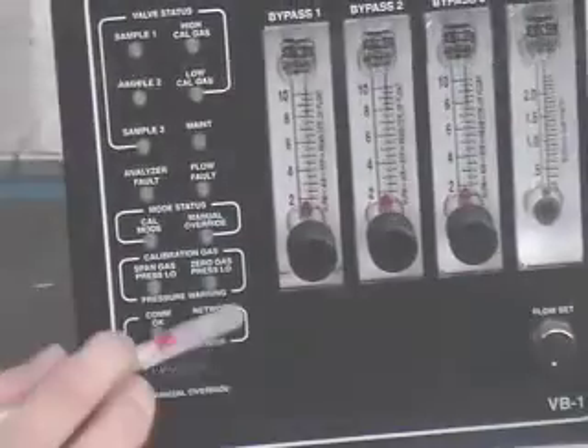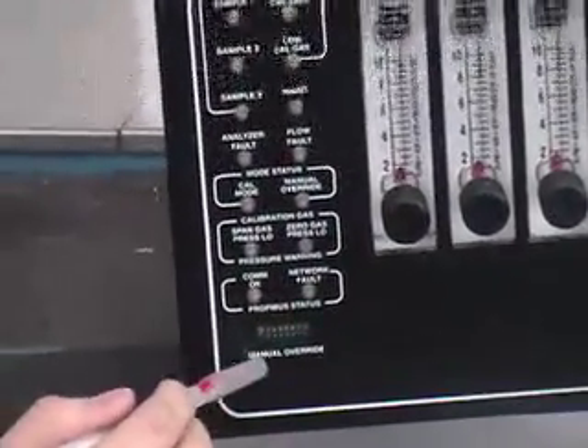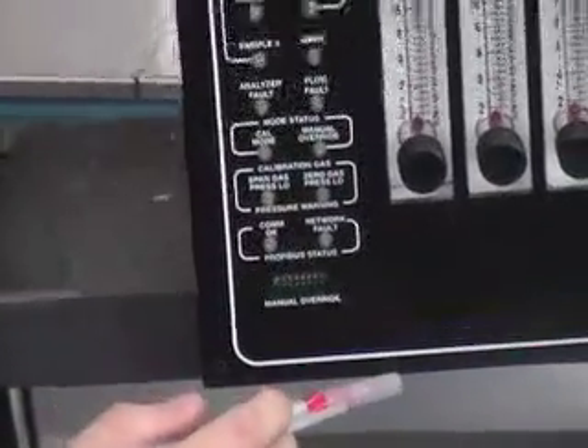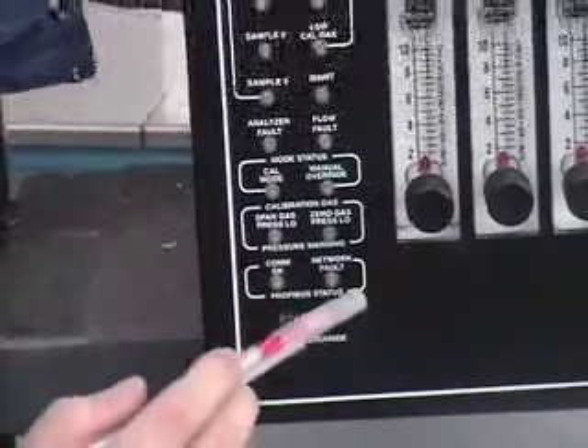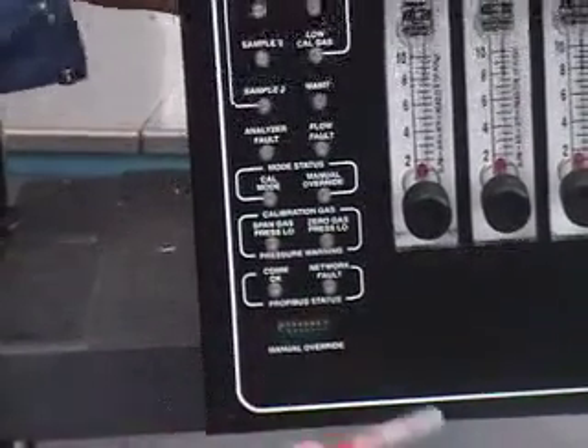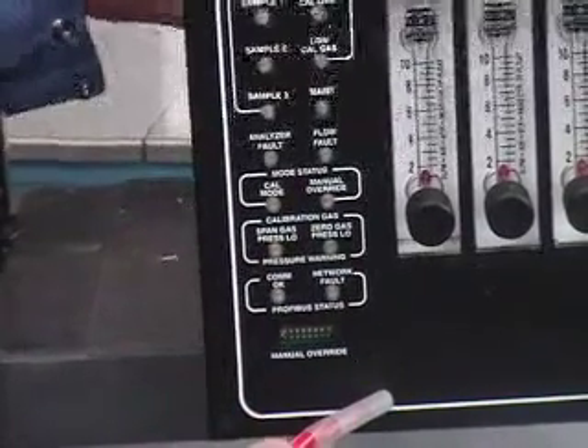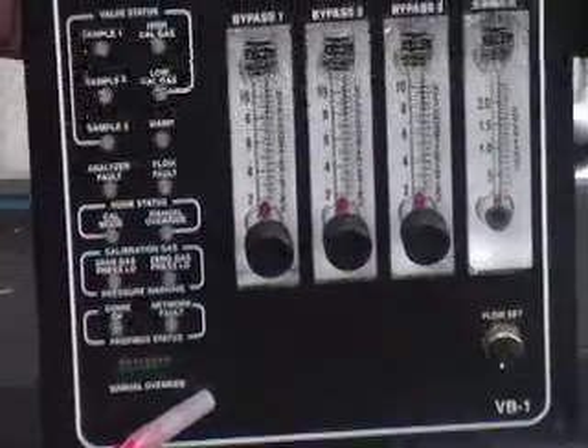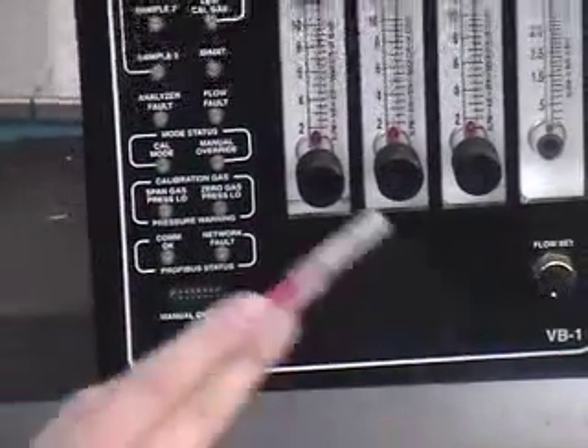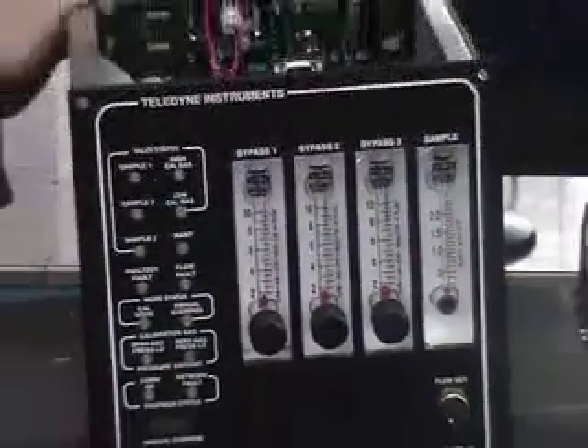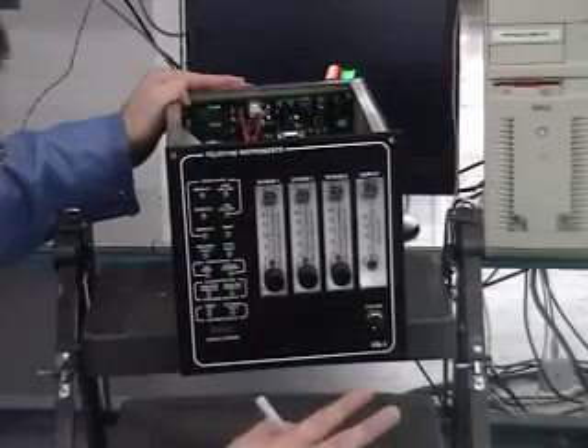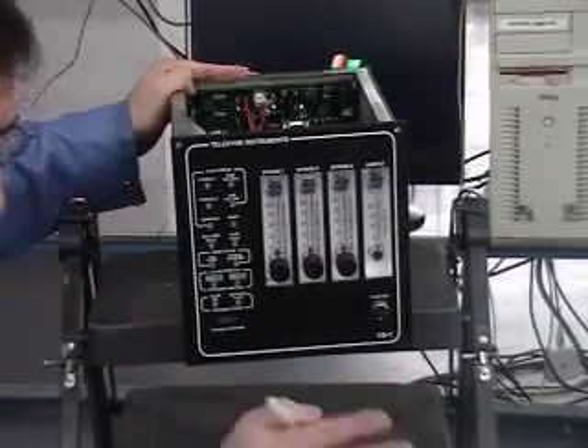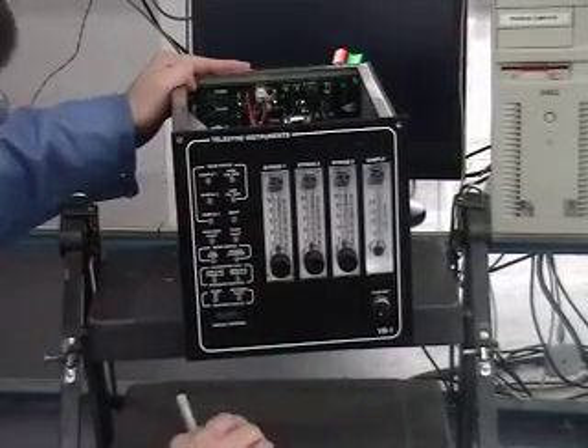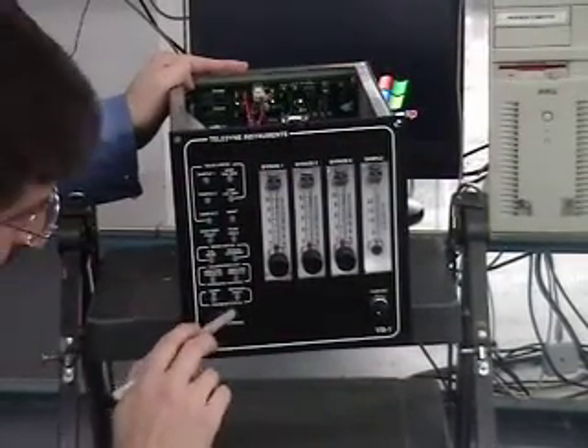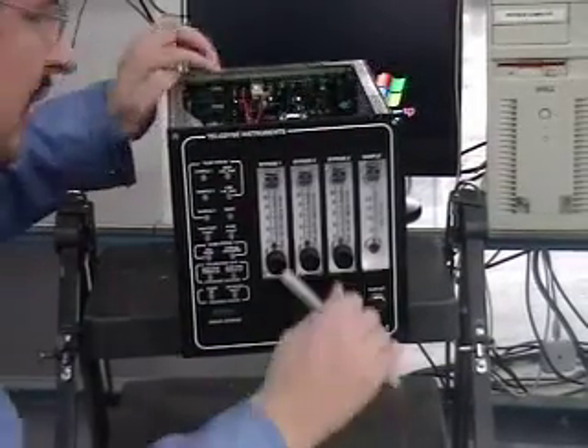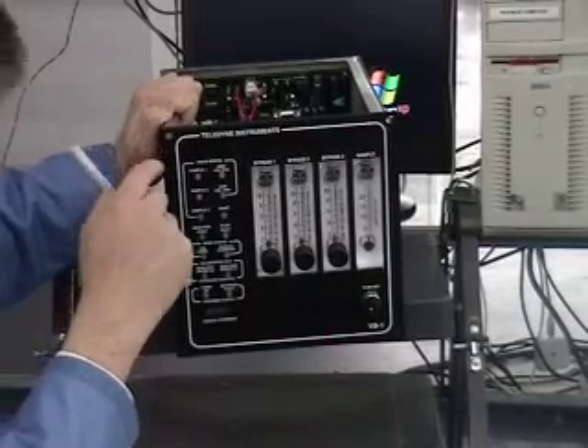You can control what mode the VB-1 is in by adjusting the dip switches on the front here. The dip switches on the back are to set the address on the Profibus network. The dip switches on the front are to set the mode. It can be set to Profibus network, it can be set to analyzer control, it can be set to manual override, or it can be set to computer override. So we'll go over this. When you power up the unit, if you want to start with a Profibus network and an RS-232 control unit, you want to have all these dip switches set down, low, or off. And of course, you set the address on the dip switches on the back.